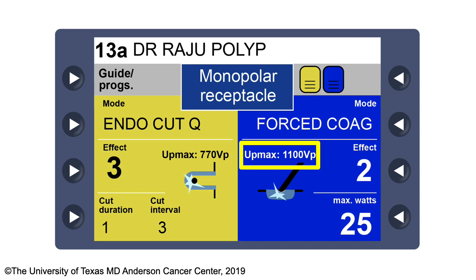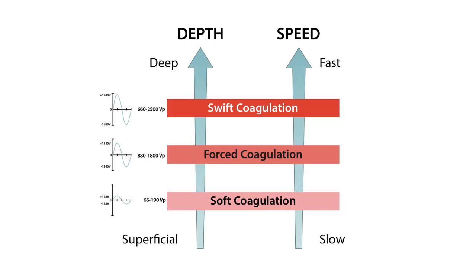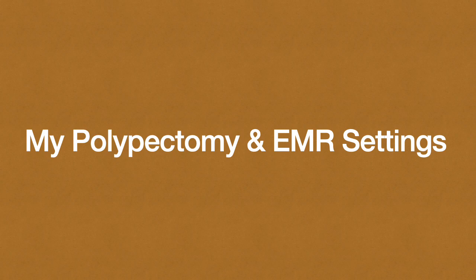Now let's look at forced coagulation. Forced coagulation is typically used for removing pedunculated polyps, and at this point I would like you to appreciate a couple of other terms. We learned about soft coagulation, where the peak voltage is less than 200, slightly higher voltage for force, and much higher for swift coagulation. In colon polypectomy, we either settle between soft coagulation for hemostasis or ablation of the edge, and forced coagulation for removal of thick pedunculated polyps.